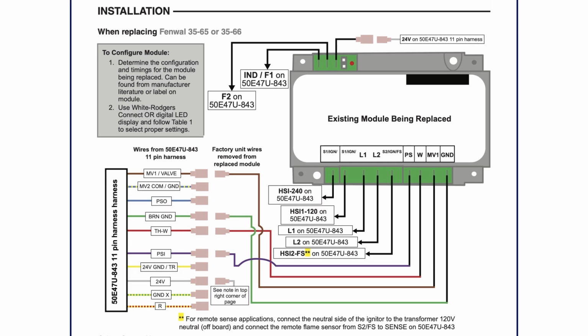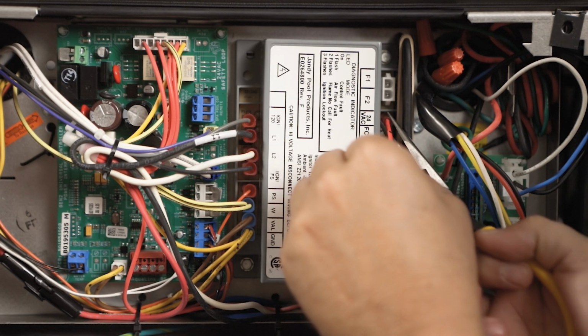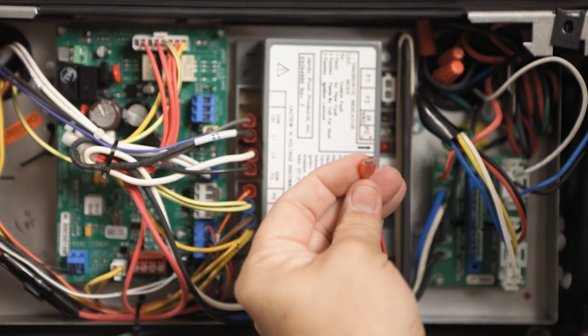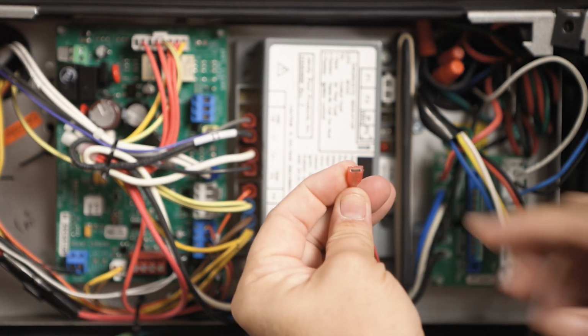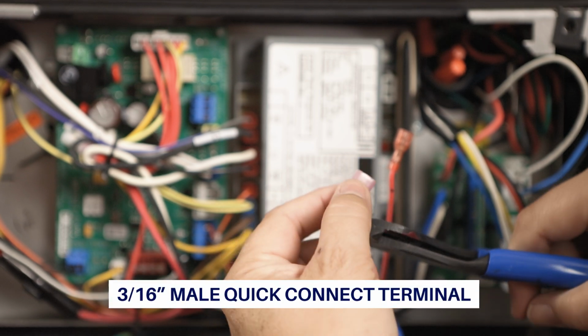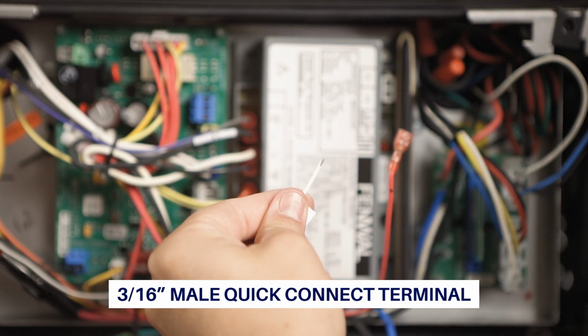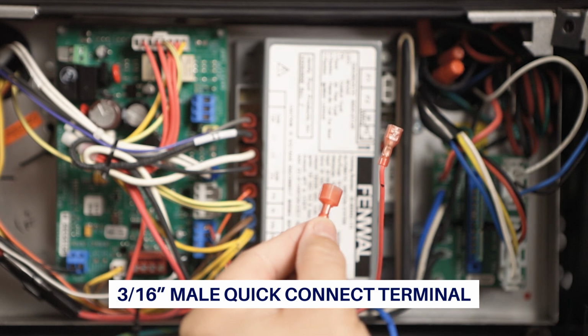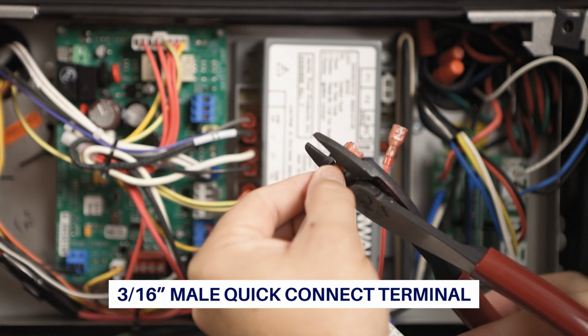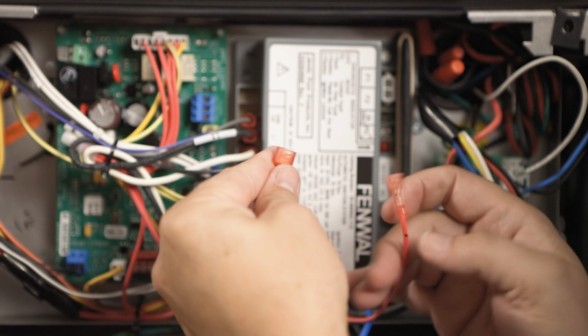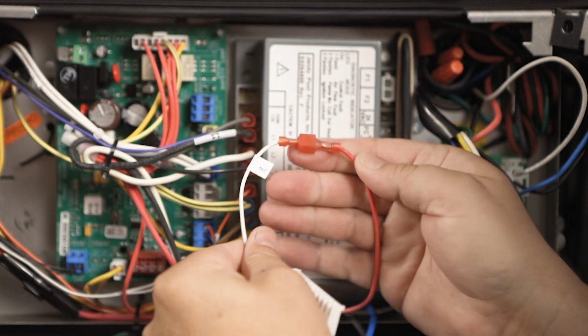Individually disconnect and transfer each wire from the existing control and connect it to the appropriate quick connect terminal on the 50E47U-843 11-pin harness. Note in the instructions when a module does not use both the 24-volt and the THW terminals. For this application, remove the wire from the 24 VAC terminal. Note if it is a 1/4-inch or 3/16 spade connector. The 11-pin harness 24V quick connect 1/4-inch male spade must be replaced with a 3/16 male spade to accommodate the existing 3/16 connector spade. Connect the 24 VAC wire to the 11-pin harness wire, labeled 24V.